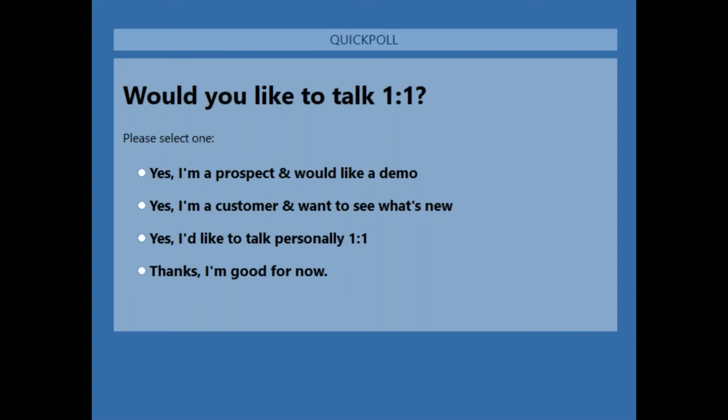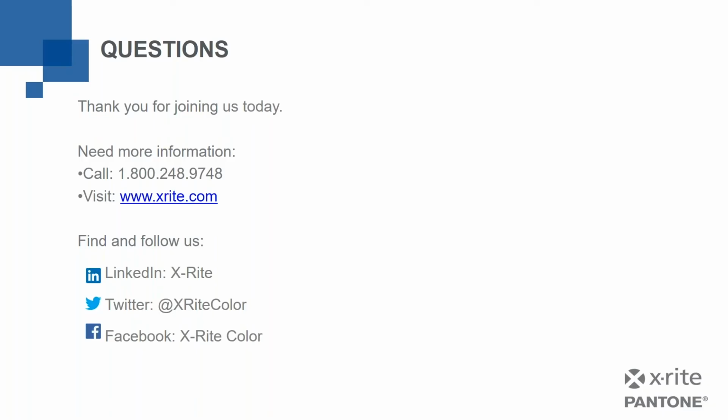They need to meet that. Well, the only way we can do an ISO 17025 calibration of a device is for X-Rite to do that at X-Rite. So recertification is necessary if you need that. But we have people who use it both ways. So NETPROFILER can be useful in doing that.